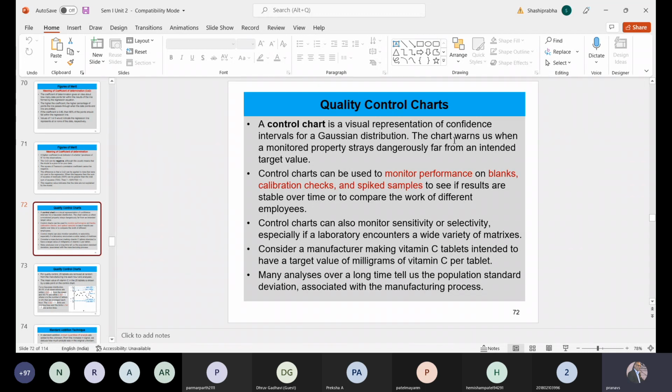They can be different, or rather they are different, but they are less in number as compared to the points which you use to prepare a calibration line. For a 6-point calibration line, you can have 2 or 3 quality control concentrations, which you can check periodically. So you need not recalibrate your equipment again and again through all those 6 calibration concentrations.